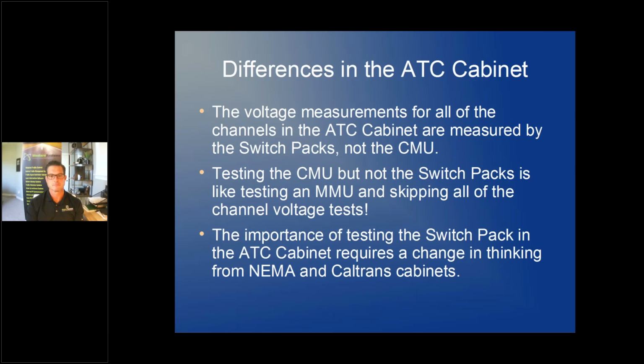The switch pack tester, the ASPT 5300, will only do the high voltage version. The reason is, currently, the vast number of cabinets in use are high voltage, probably better than 90%. If there's demand for a low voltage switch pack tester, we will likely develop one later. Because it's low voltage and because of the way the switch pack works, we may even be able to make it a handheld device.